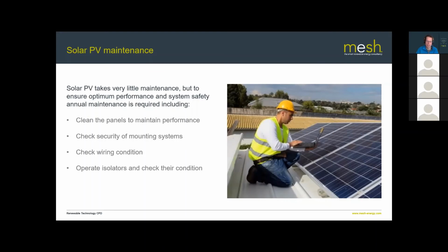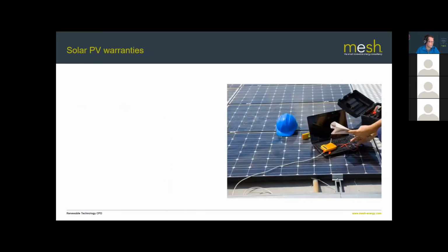Checking the condition of isolators. Again, isolators can be in quite exposed locations. They can be subject to all kinds of mechanical and weather damage. So it's worth just making sure the isolators are still working correctly, checking that cables are done. And then obviously just use monitoring software to diagnose and fix any faults, which is what this gentleman here is doing.